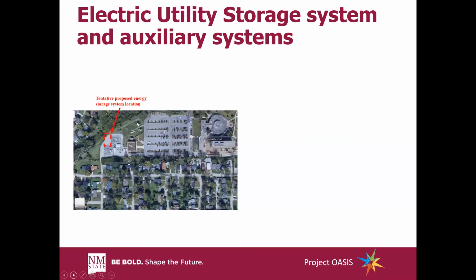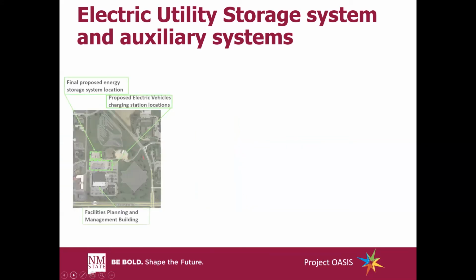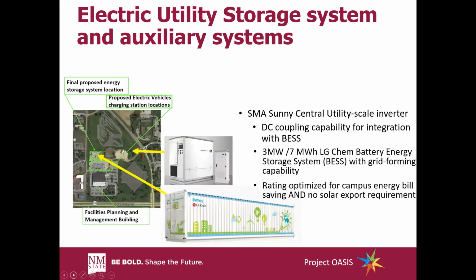To meet the requirements from the previous slides, we're proposing three 1 megawatt LG utility battery energy storage systems. LG provides a turnkey solution for a highly efficient 1 megawatt, 2 megawatt hour system with a PCS efficiency of 98.7%, which is shipped in a shipping container with its own power conditioning system, or PCS. This system is also capable of operating in an islanded or grid forming mode, which could be a very valuable feature should the BSU campus decide to operate it as a microgrid.